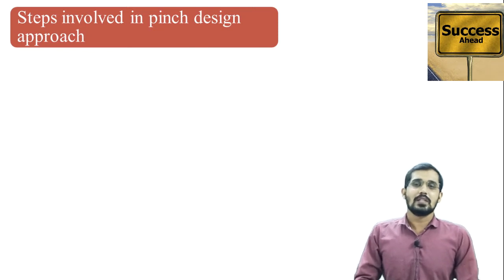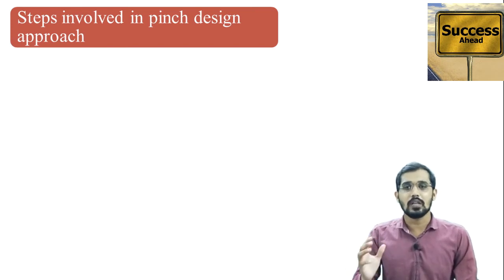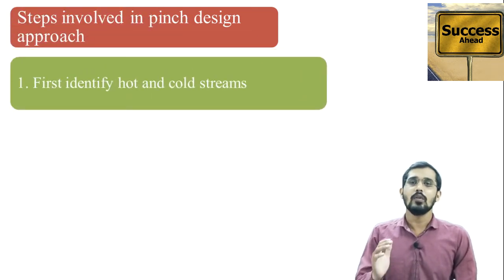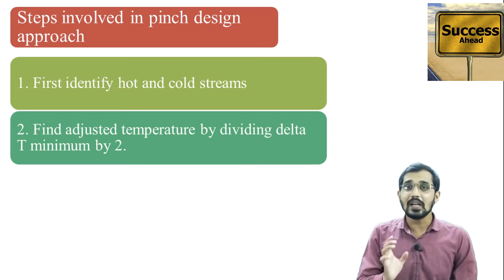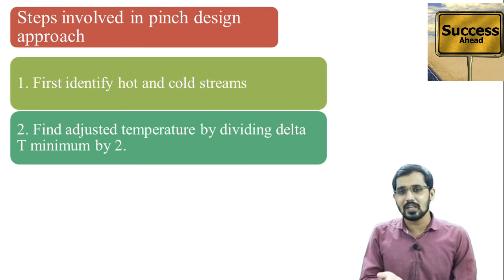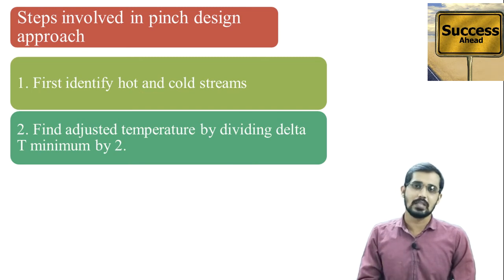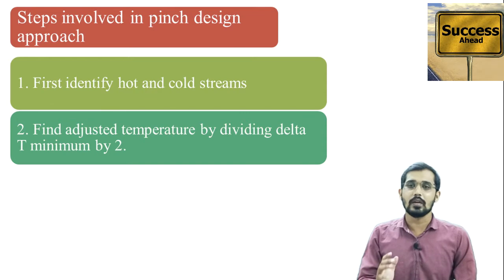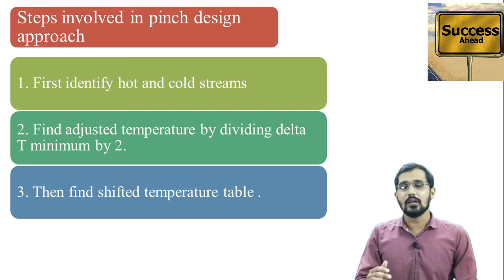Now we will see the steps involved in the pinch design approach, which is also known as the temperature interval method. The first step is to identify all hot streams and cold streams. After that, find the adjusted temperature using ΔTmin. To find it, divide ΔTmin into two equal halves — for example, if ΔTmin is 20°C, the adjusted temperature is 10°C. In the last lecture, where ΔTmin was 10°C, the adjusted temperature was 10 ÷ 2 = 5°C. The next step is to find the shifted temperature table.